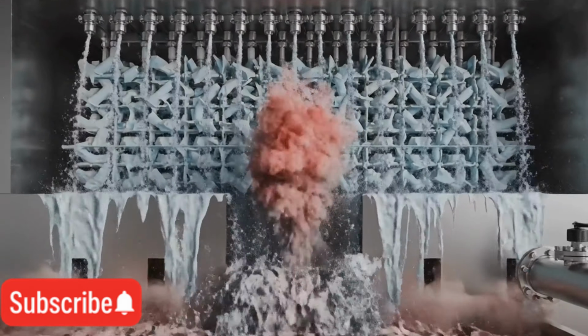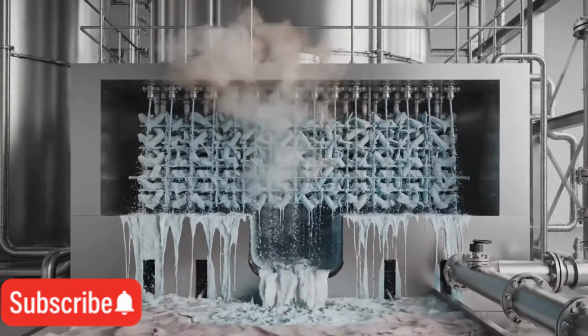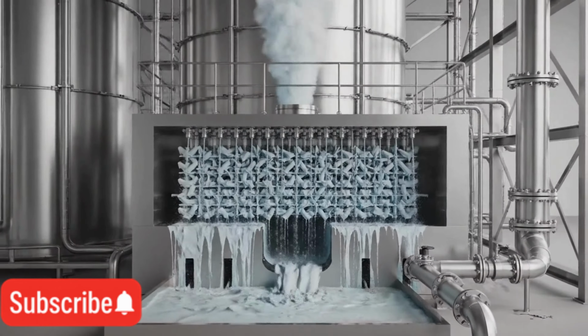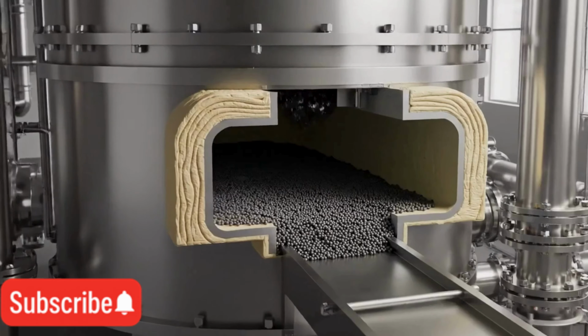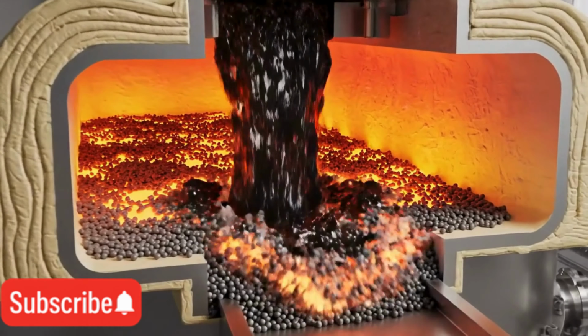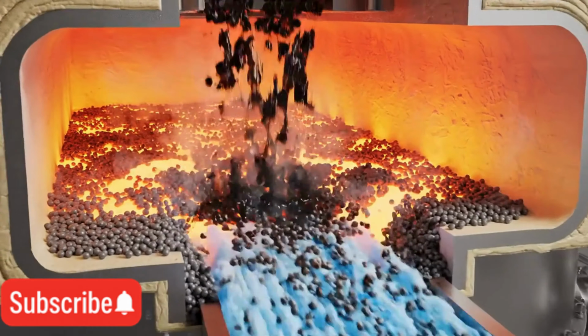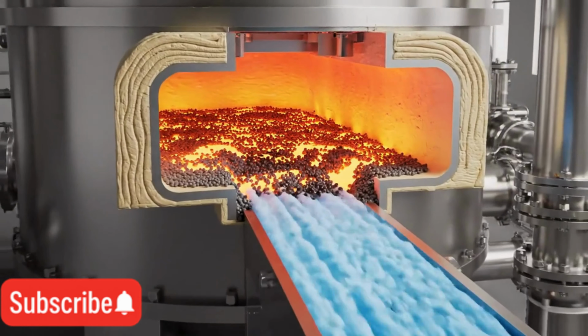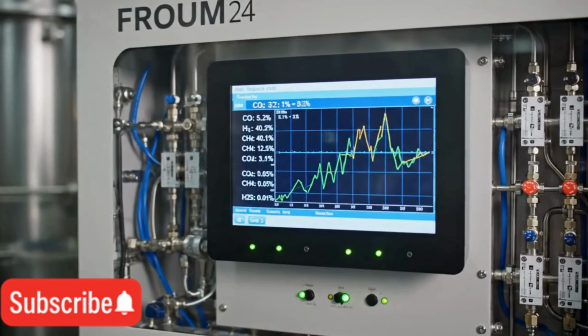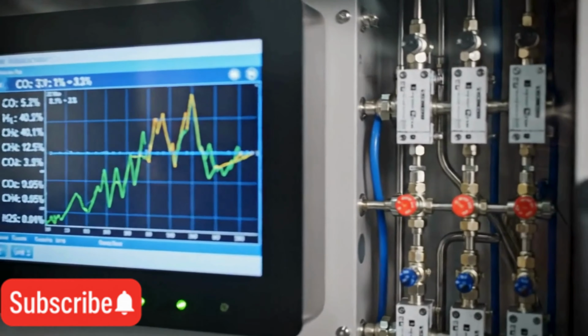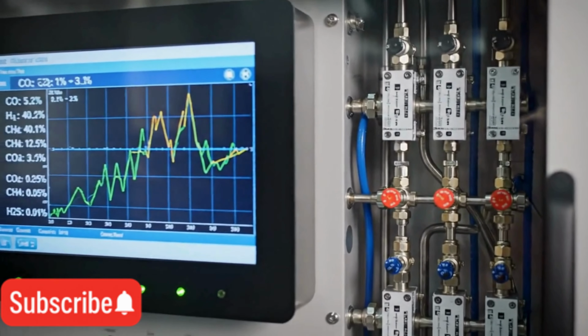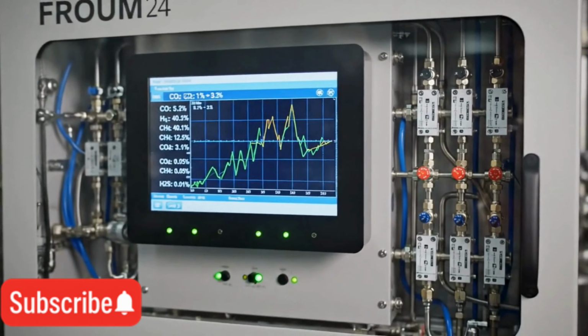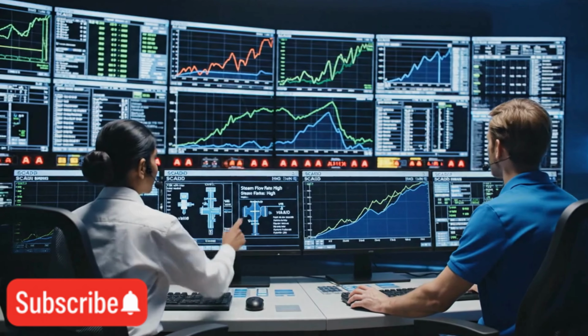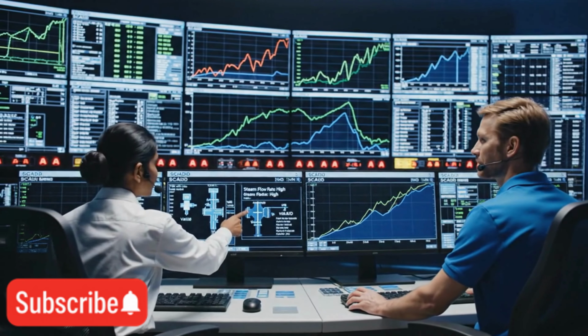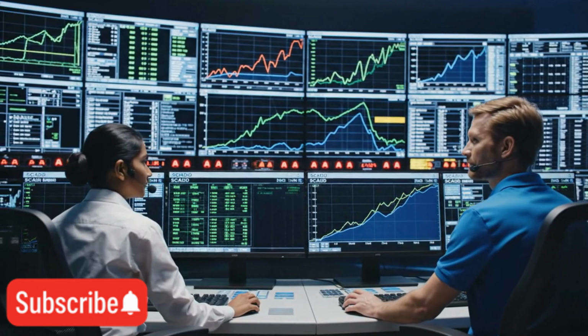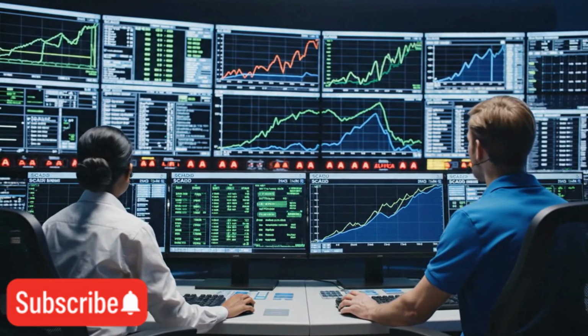An integrated wet scrubber then washes the gas, neutralizing acid gases like sulfur dioxide. For high-quality syngas, a catalytic reactor is used to crack heavy tars and hydrocarbons into lighter gases, preventing fouling in downstream equipment. Online gas analyzers continuously measure the composition of the clean syngas, feeding real-time data back to the plant's control system. A distributed control system, or DCS, manages the entire process through a SCADA interface.